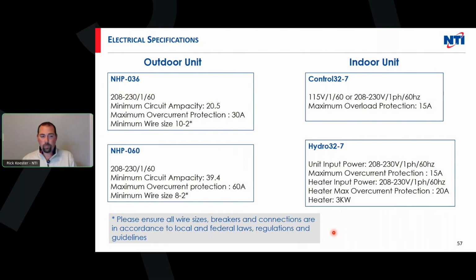So if I put 115 in and I put a 208, 230 volt circulator in, there's going to be a problem, vice versa. I put 208, 230 in and I have a 115 volt circulator, I'm going to burn some circs out. So 115 is going to be my communication to most contractors, and I don't see any reason why to do anything other. Hydro box is 208, 230 volt only, so that's going to be input power. We have a 15 amp breaker for that. And then if we were going to use 3 kW element inside of it, that would be an external 208, 230, and that would be on a 20 amp breaker.